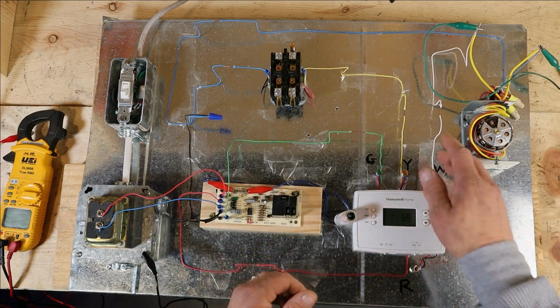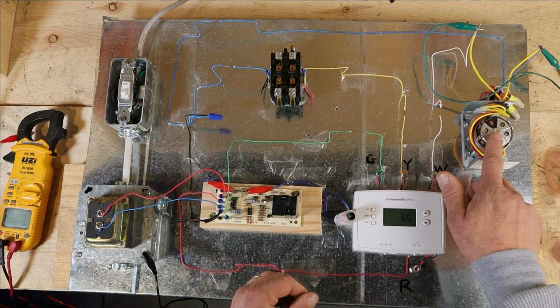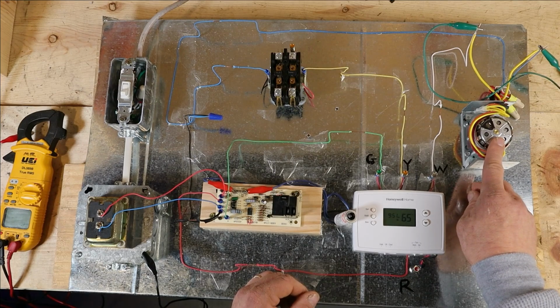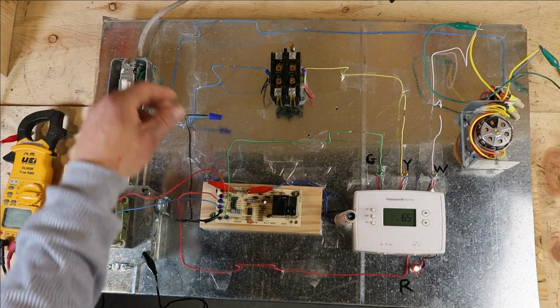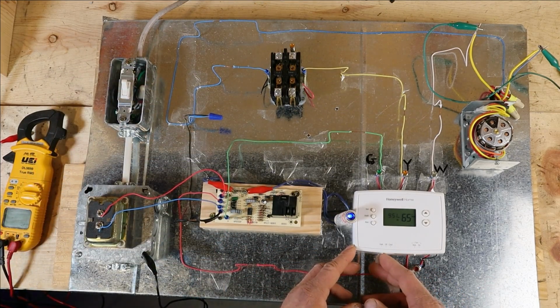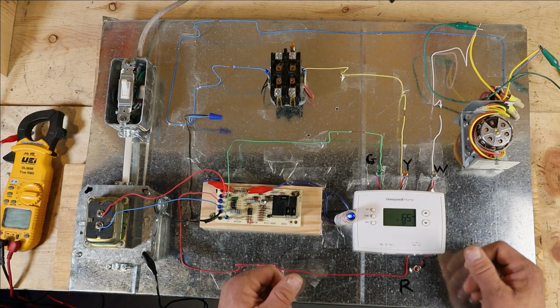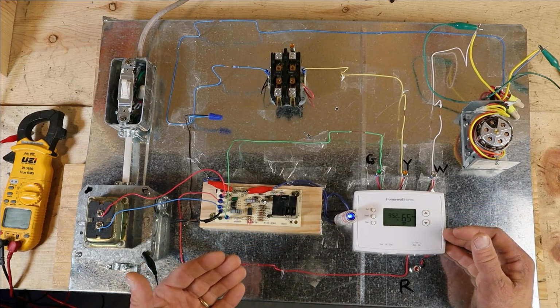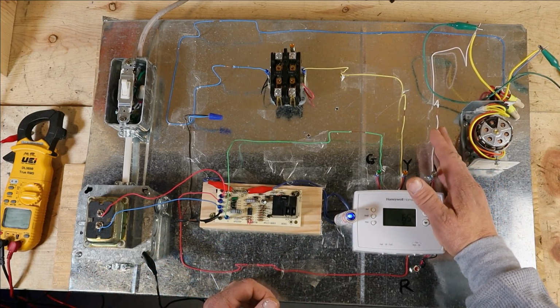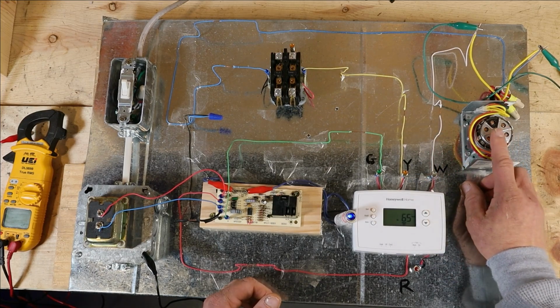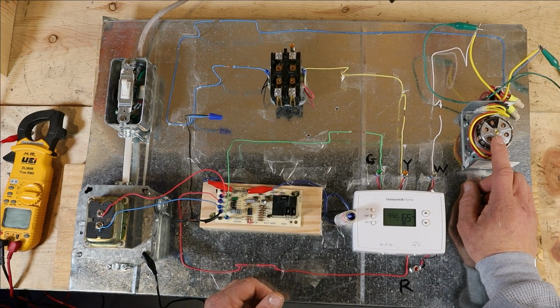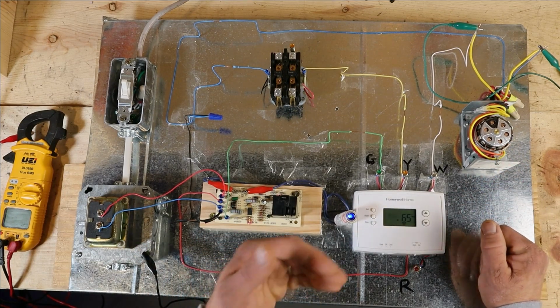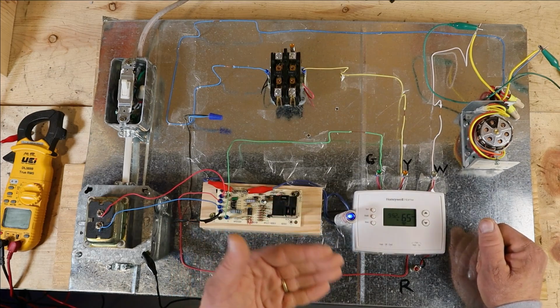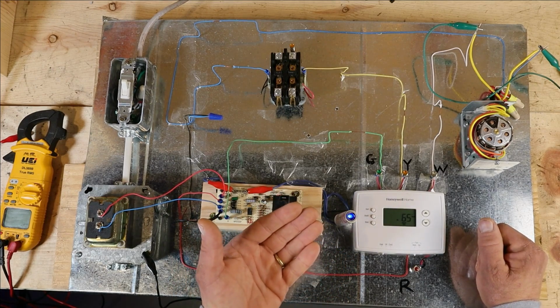Now let's assume the problem wasn't a bare wire touching metal and the problem was with the motor itself. It's no longer providing the resistance we need to prevent a fuse from being blown. So what would happen here is when we turn our power on and we go into heating mode, we immediately have a short and our fuse blows. Now what this tells us is because our secondary is floating, it can't possibly be a wire touching metal that's blowing our fuse, and now we know we have a component in the circuit that is no longer providing the resistance we need to prevent these fuses from being blown. So now I know automatically I'm looking for a component in the heating circuit that usually provides resistance that now does not.